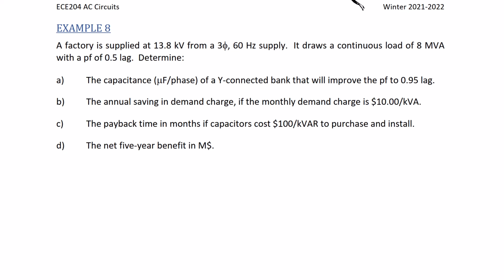Determine the capacitance in microfarads per phase of a Y-connected bank that will improve the power factor to 0.95 lag, the annual saving in demand charge if the monthly demand charge is $10 per kVA, the payback time in months if the capacitors cost $100 per kVAR to purchase and install, and finally the net 5-year benefit in millions of dollars.